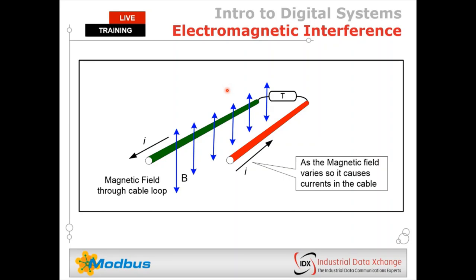The easiest way to prevent electrostatic interference is to increase the distance between your Modbus cable and the source. Anything above 60 volts DC or AC should be separated 10 to 50 centimeters from your Modbus cable. Electromagnetic interference is caused by noisy devices such as VSDs and motors that create a magnetic field. Again, move your cabling away from the source. Industrial standards implement shielding on cables — it's very important to use shielded cable, with the shield grounded at multiple points to drain noise to a functional grounding point.